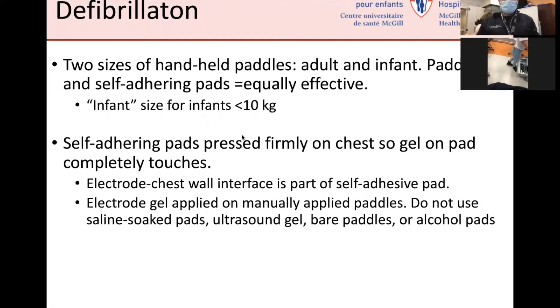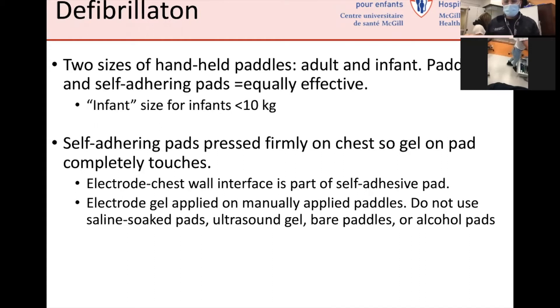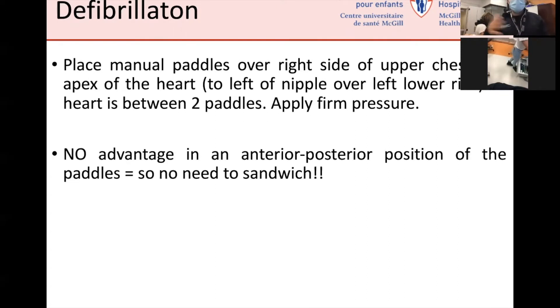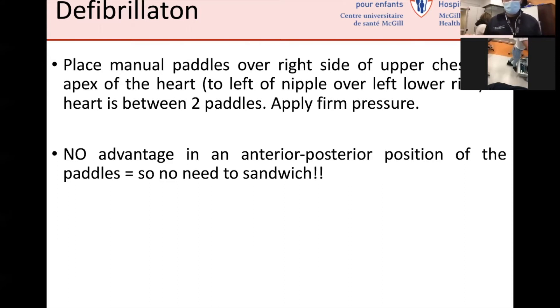When using self-adhering pads, press firmly on the chest so the gel completely touches the skin. There is a chest wall electrode interface built into the pads. Do not apply saline, ultrasound gel, or alcohol pads — just stick the two pads as shown on the mannequin. There is no proven advantage to the anterior-posterior sandwich position; personally, I prefer aiming for the apex and center of the chest.